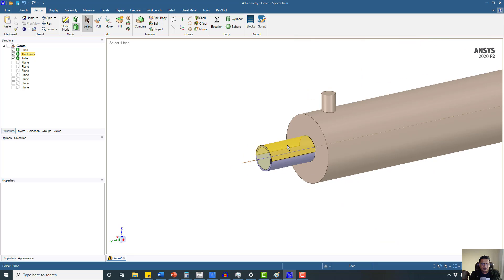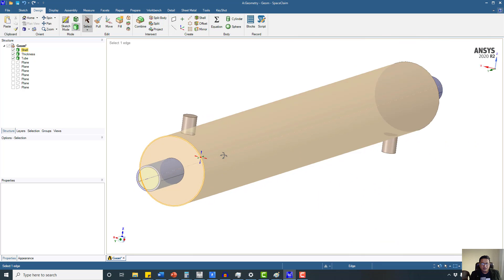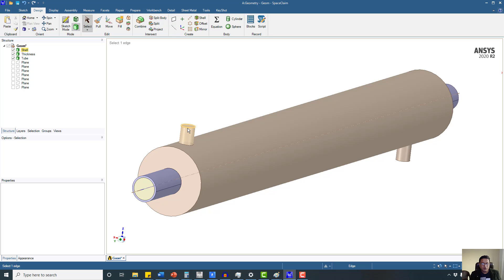There are two things we want to achieve. One is that we should have the proper orientation for the shell and the tube. For the shell, this is very important because the steam, being lighter in density, should flow naturally from the upper direction downward. Otherwise we would have to use two-phase type pumps, which are not very common and have problems, so I won't go into discussion about those.